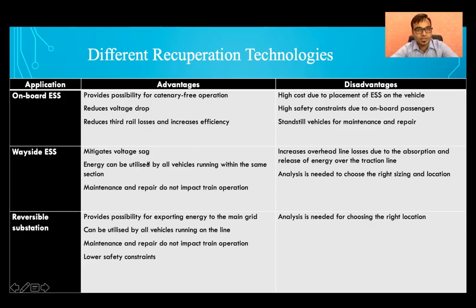For Wayside ESS, the advantage is that it mitigates voltage sag, and the energy can be utilized by all vehicles running within the same section. Its maintenance and repair will not impact train operation since it is placed in the substation. The disadvantage is that it increases overhead line losses, because energy generated from the rolling stock has to be fed back to the substation and then fed back again when required, making line losses a little higher. Also, analysis is required to choose the sizing and location of the wayside energy storage.